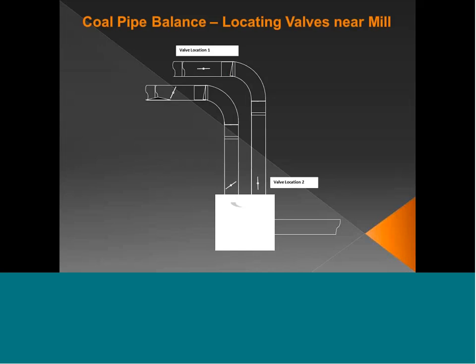If you put a coal valve very far downstream in a milling system or a pulverized coal delivery system, the milling system might continue to deliver coal to that pipe, and all you're going to do is take away transport air, as in this depiction here, and you're going to create coal layout. If you use coal valves close to the pulverizer, they are better at creating a back pressure internal to the mill and preventing some of the coal from ever getting to this pipe. Now realize that as you close that valve, you will also take away transport air, so you will slow down the coal that's in the pipe.